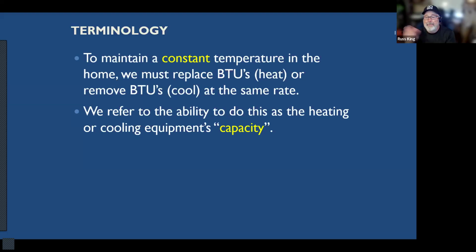We can calculate how fast they're coming in, and so we can size an air conditioner that can remove it at least at the same rate. So we want to maintain a constant temperature. The ability to add or remove heat is what we call the equipment's capacity, sometimes referred to as the output. So the load is what the house needs, and we can calculate that. The capacity is what the equipment gives us, and we can look that up in tables that the manufacturer provides. Sizing equipment is the art of balancing what the house needs with what the equipment gives you. We'll certainly talk more about that, and if you're interested in the whole design process, we have classes on that too.